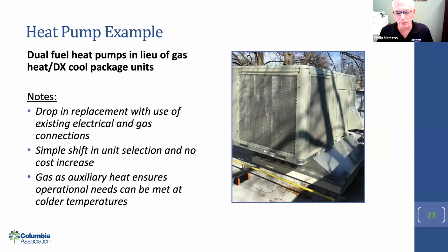and cooling package units are dual fuel RTUs. These are basically units where we have decided to change out standard RTUs for a dual fuel heat pump that utilizes the heat pump technology as the basis for heating and cooling. But due to our climate, we also have gas as auxiliary heat whenever we need it. Now, our temperatures can range from into 100 degrees in the summer to single digits in the winter. So there are times that we could use some gas to ensure operational needs. Next, please.